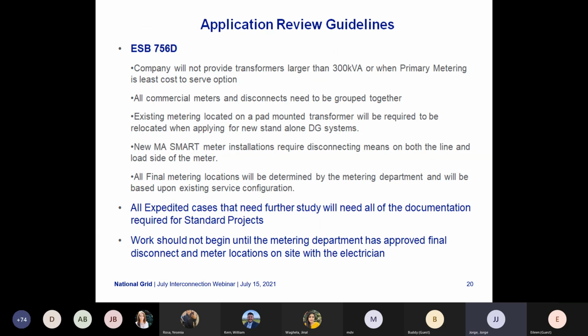So in some of the application reviews, the company will not provide any transformers larger than 300 kVA when primary metering is the least cost to serve option. All commercial meters and disconnects are required to be grouped together, and that will be determined by the metering department during the construction process. Any existing metering located on a pad mounted transformer, unless it's a behind the meter system, will need to be relocated. All MA smart meter installations require disconnecting means on both the line and load side of the meter. Any expedited cases that need further study will require all of the documentation required for standard projects. So if it's deemed during a screening that an application needs to go to further review, and the application didn't require those documents, then it will require all of the standard documents to proceed further. And then no work should begin until the metering department has been contacted during construction to have all the final locations approved. Next slide, please.